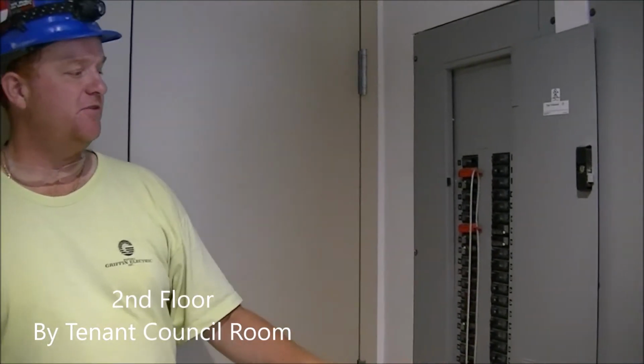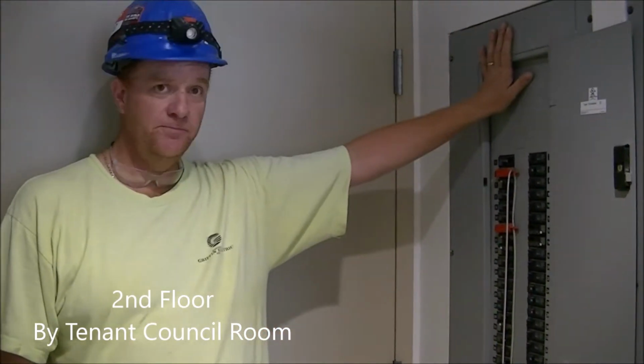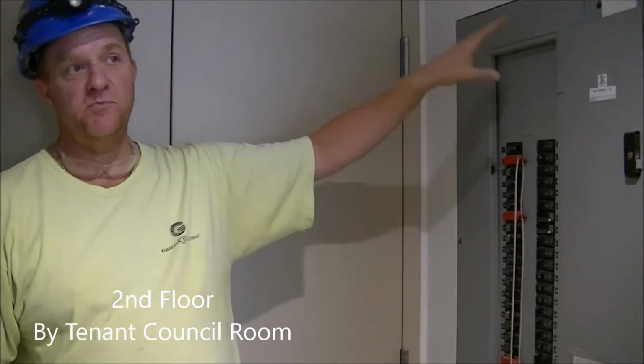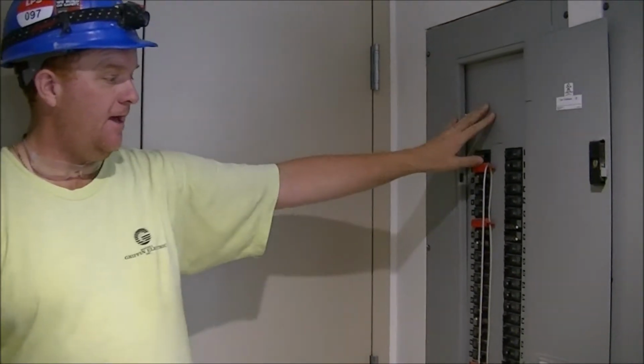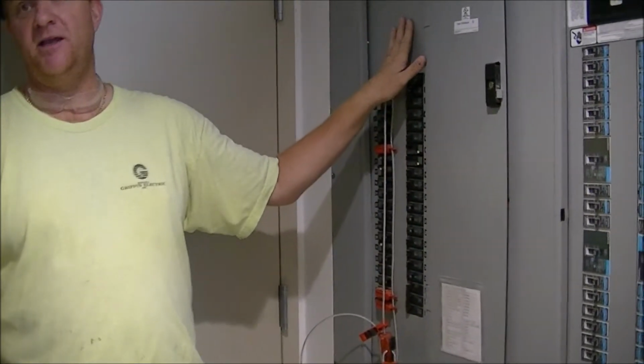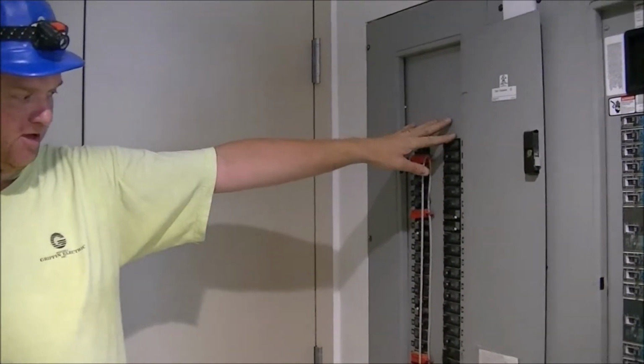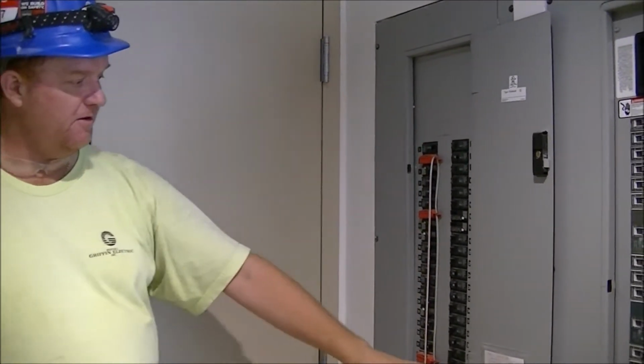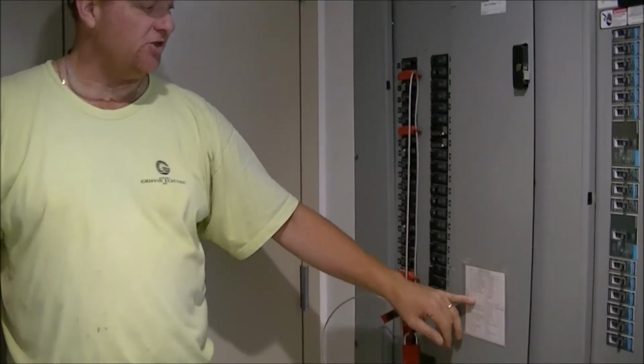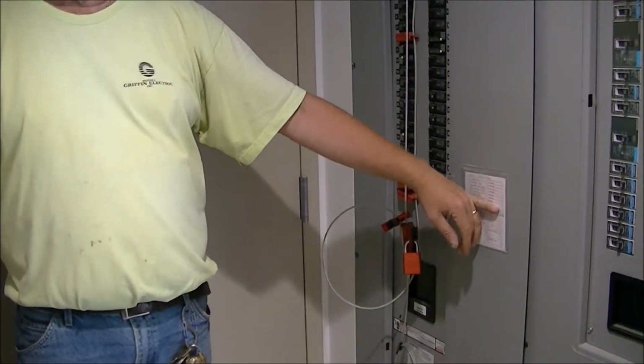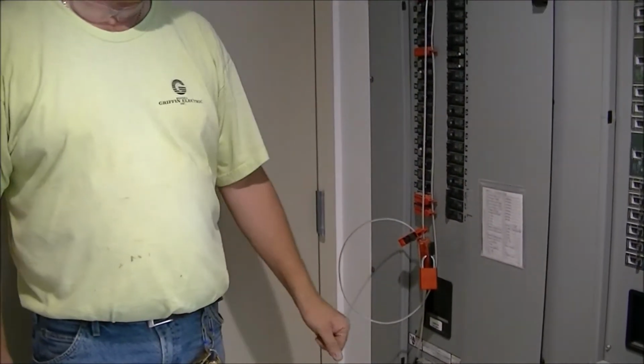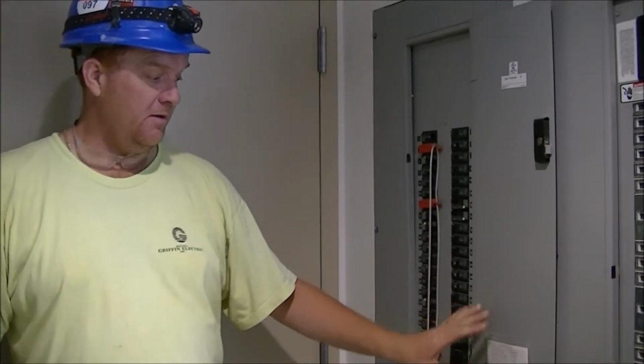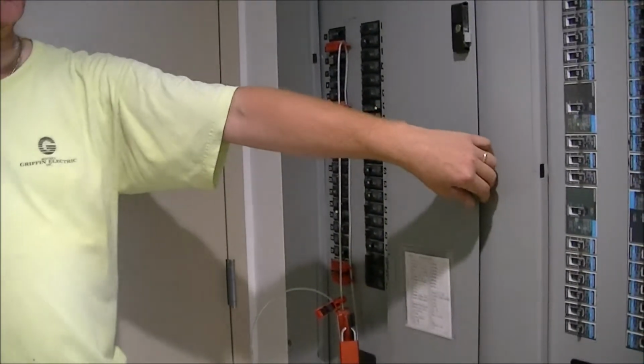So we're up on the second floor now, two panels for this area. This is L2, fed from panel SDSB, which we're going to go to shortly. This low voltage panel is 120-208, general lighting and power and miscellaneous stuff. It also does the dryers and washers for the floor laundry, and some small exhaust fans that are only 120-208.